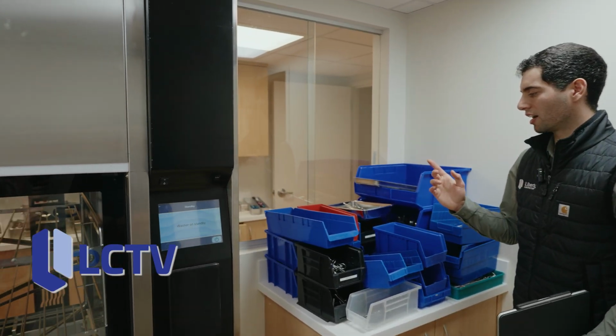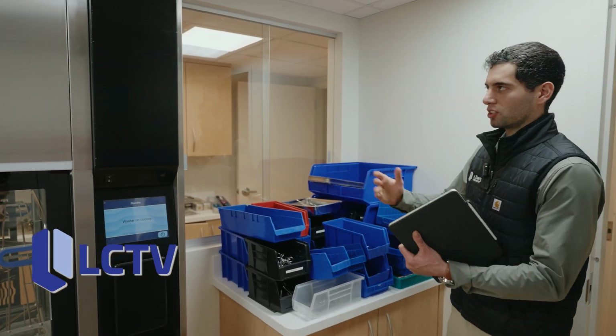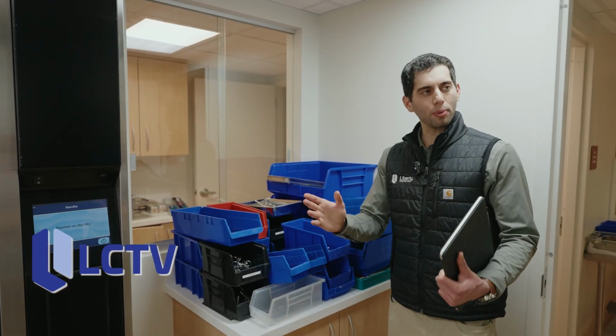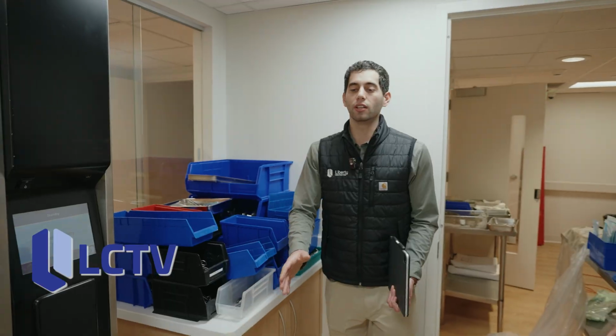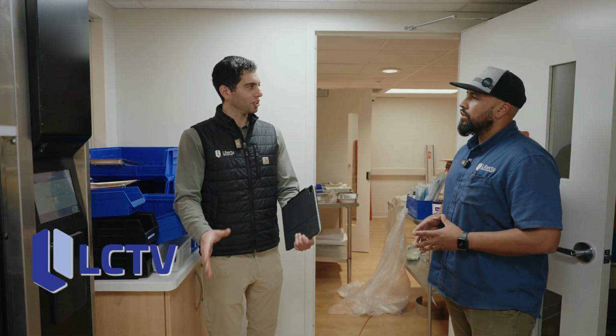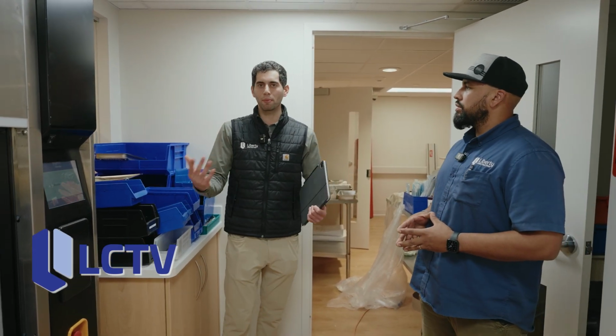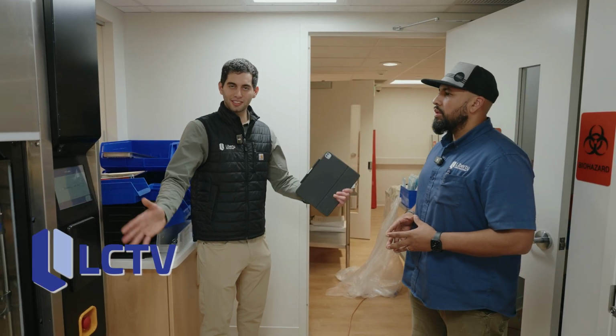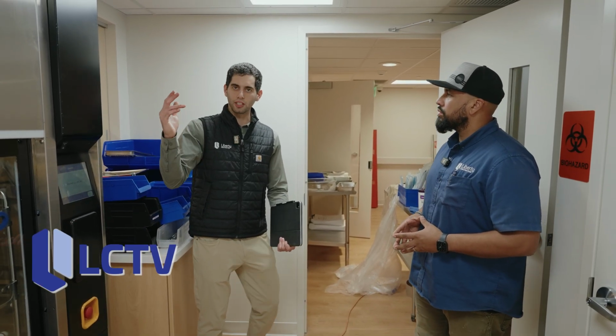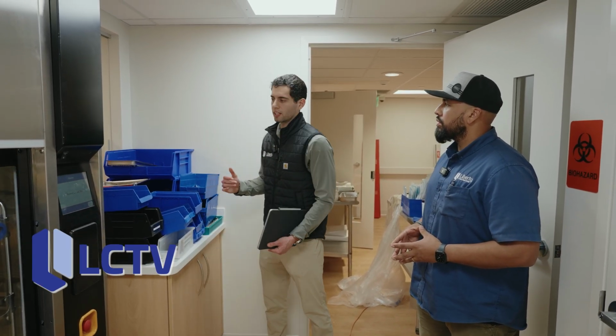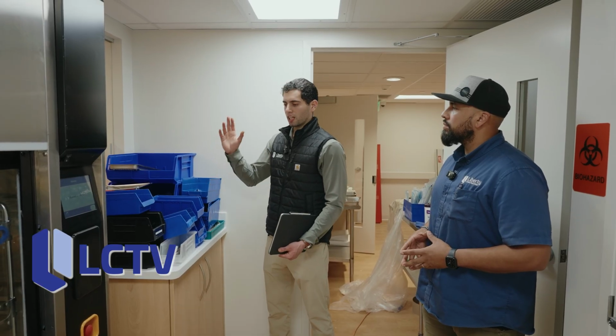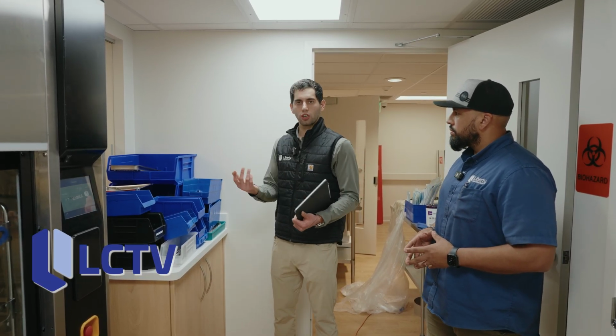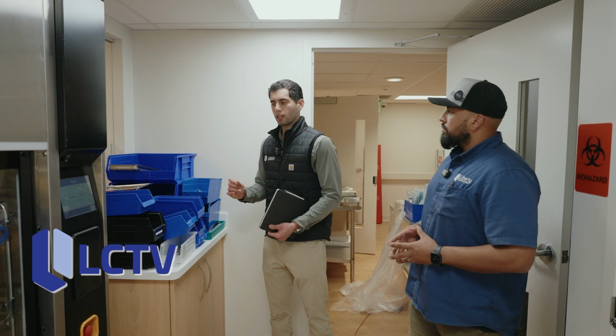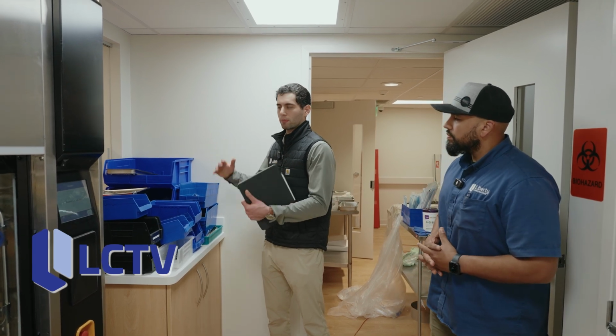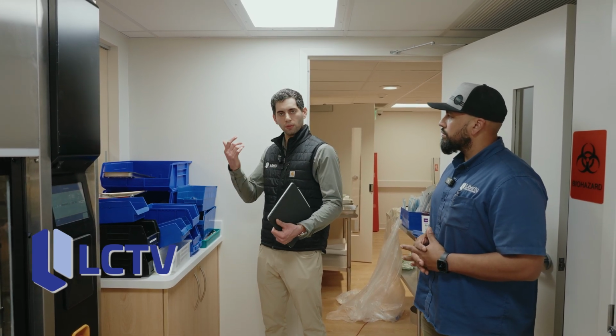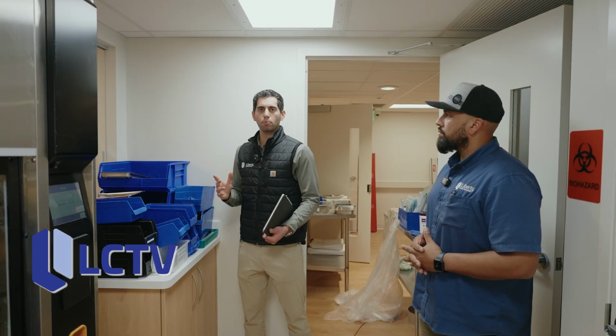But it begs the question: because we separate clean and dirty, we're definitely going to need negative pressure on the dirty side to keep any contaminated air particles there and just get filtered out through the return grills in the ceiling. Which means we definitely need to make sure that even the returns are balanced perfectly, so that air that comes out immediately gets filtered back in the return. But we also need to seal any points of leakage.